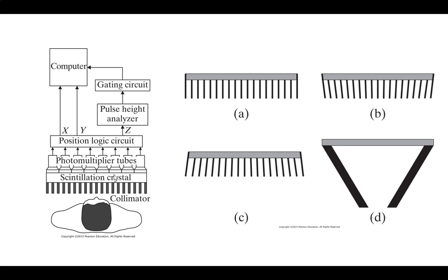The deeper in I go, the bigger the relative pixel is that I'm dealing with, the image where you're actually resolving it. So it does have a spatial aspect: it determines how big the resolved region is in the body. That's why we want this close, because we don't want the depth-dependent blur to grow. We want these to be fairly long because it keeps this tight so it doesn't grow too bad.